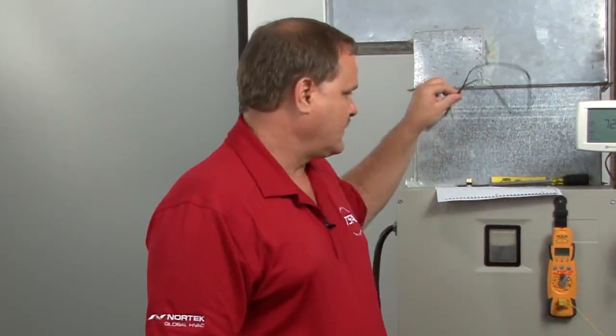Now, the other thing is, you go out on a service call and the unit's froze up. Why did it freeze up? Well, it could be a defrost problem. It could also be a sensor problem. So the first thing I'm going to tell you to do is check the sensors. If the sensors ohm out and that's not a problem, you've eliminated that. Your next step is to force a defrost. And if you can force a defrost and the sensors are good, then more than likely you don't have a defrost problem. You've got a refrigerant flow problem.